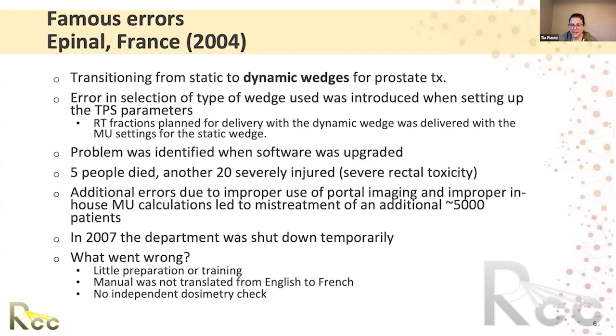Finally, there was no independent dosimetry check to ensure that the MUs for the dynamic wedge made sense. Of course, you're going to be delivering a much higher number of MUs for a hard wedge to account for that transmission than you would for a dynamic wedge.